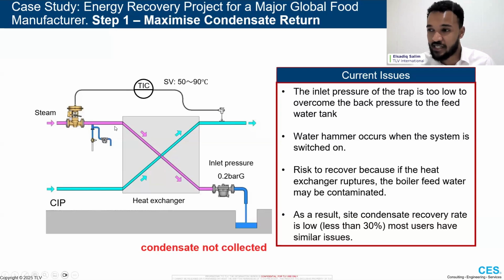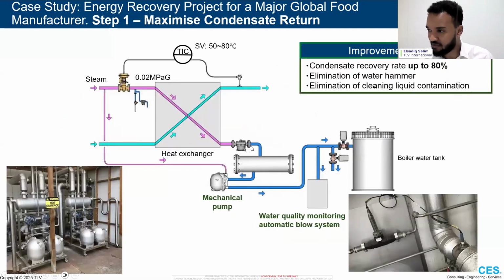Not to mention, the second issue is that even if there was not a pressure issue, returning the condensate imposes some risk on the boiler system, because if this heat exchanger were to rupture because of water hammer or corrosion from backed up condensate, they could get the CIP fluid, those chemicals, going back into their boiler system, which is another risk that the company, the site, could not afford.